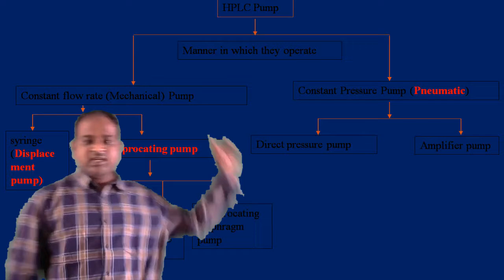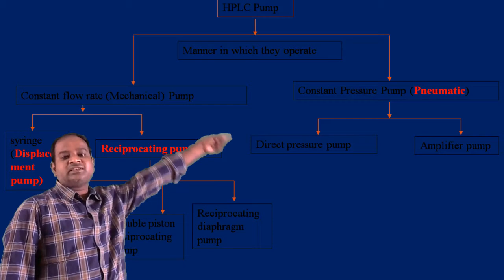Next, HPLC, how the pumps are operated. That is, the manner in which HPLC pumps operate. It is divided into two types. One is constant flow rate, that is the mechanical pump. The other is constant pressure pump, that is the pneumatic type. Constant flow rate mechanical pump is again divided into two types: displacement pump and reciprocating pump. This reciprocating pump is again divided into single piston reciprocating pump, double piston reciprocating pump, and reciprocating diaphragm pump. In the same way, pneumatic is also divided into two types: direct pressure pump and amplifier pump.